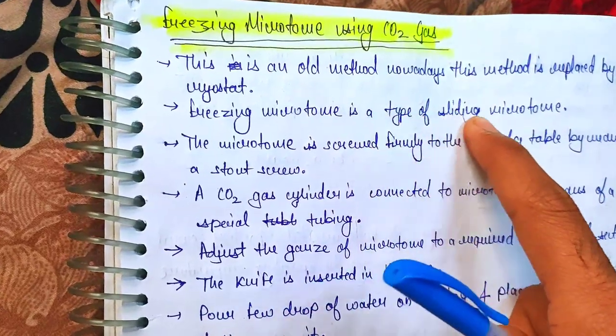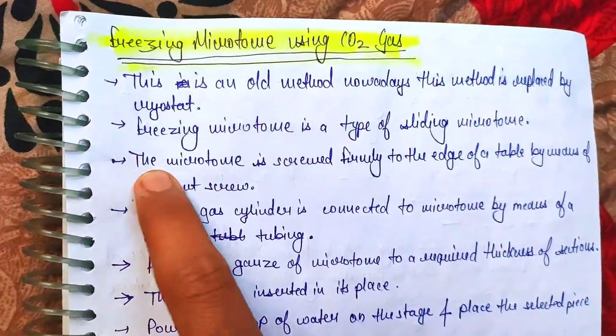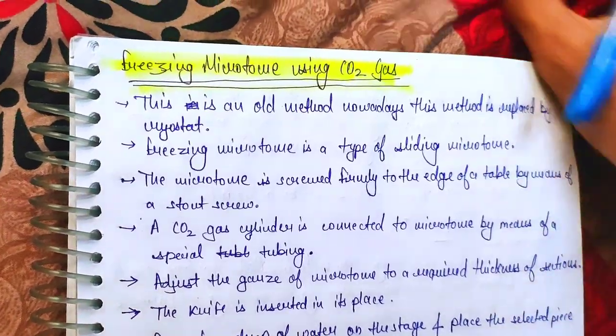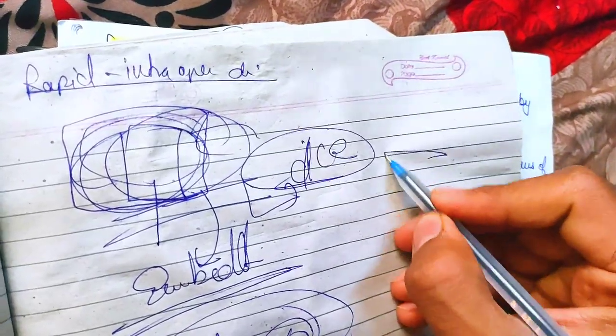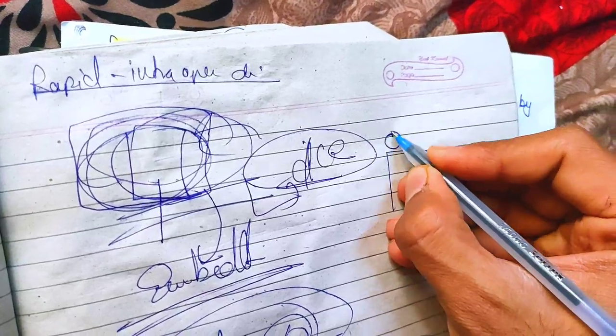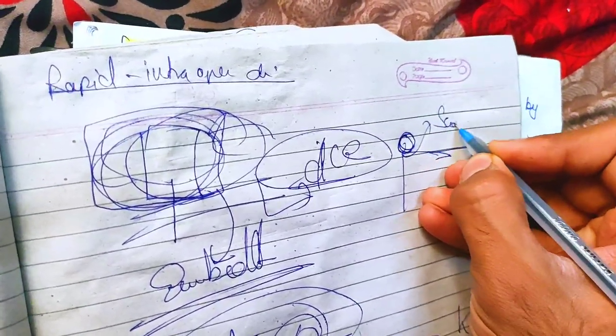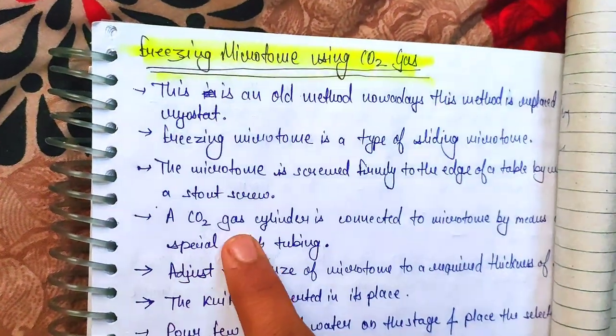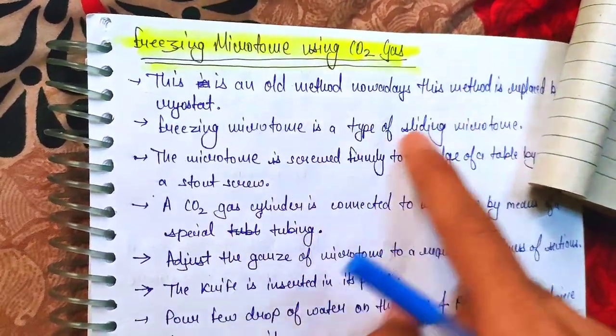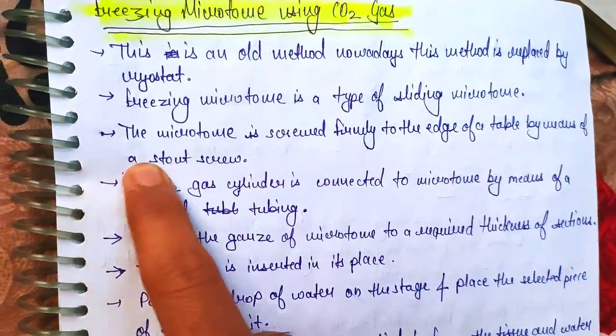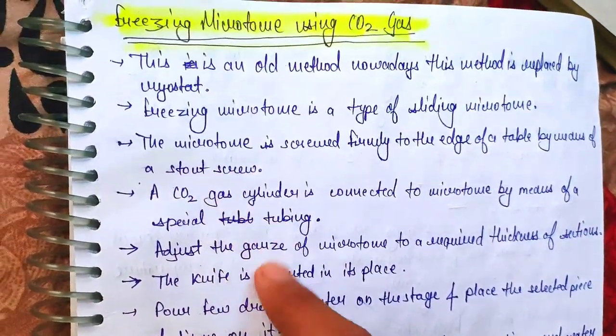The first step is to screw the microtome firmly to the edge of the table by means of a stout screw. This ensures the microtome is stably fixed before use.